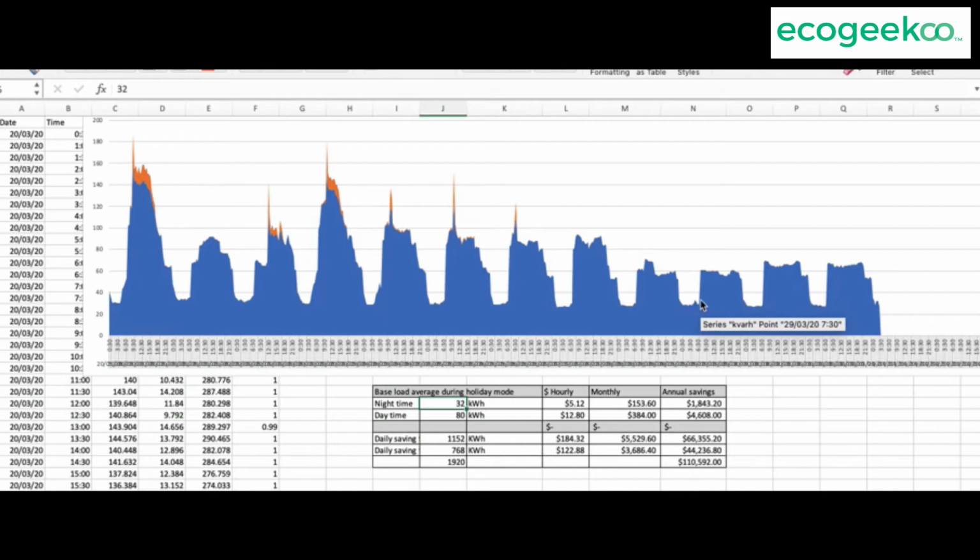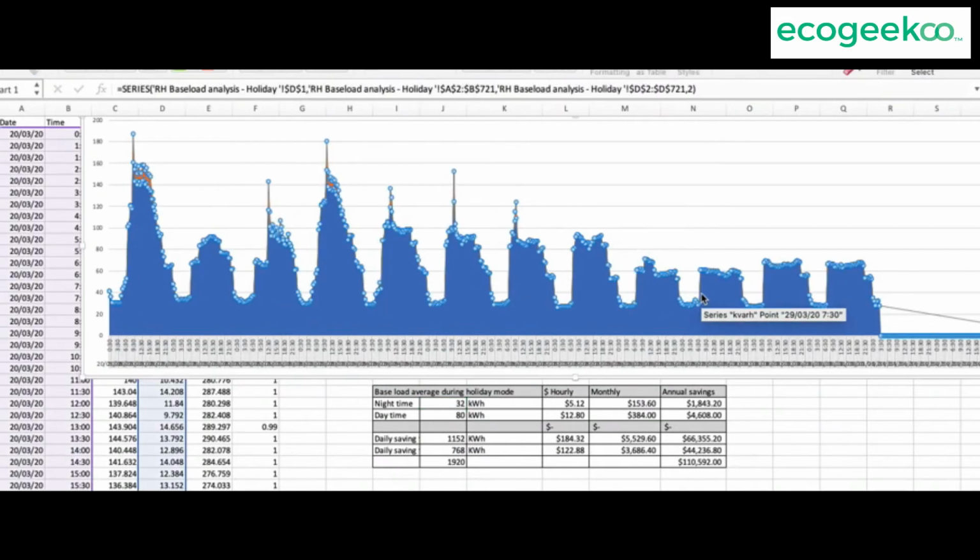So you see it's also coming in at a particular point of the day and then dropping off. So about 10 p.m. a load comes on, at around 6:30 a.m. it shoots up, stays pretty consistent all day, then starts dropping off at 9 p.m. and then drops off again at 10, and then towards midnight it goes back to this shoulder load, this nighttime base load. So that tells us that something is still working to a schedule.